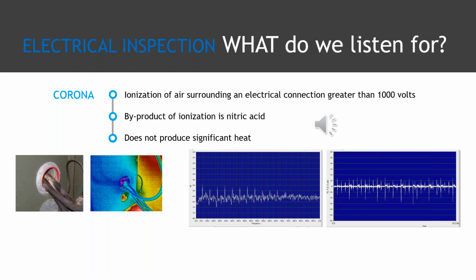So by definition, it's just ionization of a connection or an insulator at greater than 1,000 volts. But the byproduct of that ionization of the air is nitric acid, which is going to start to break down the insulating materials and break down the insulator itself. So it's not going to produce a whole lot of heat. In many cases, you don't pick up corona using infrared. So it is a failure mode that's best addressed with ultrasound.